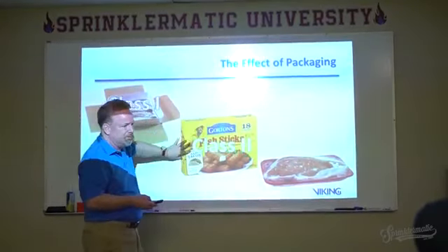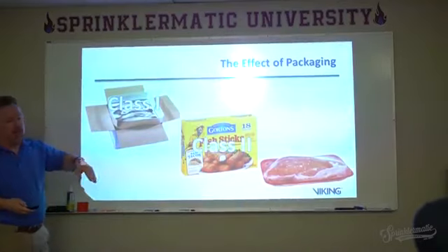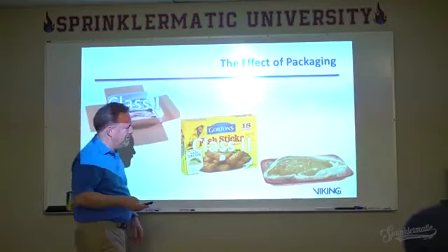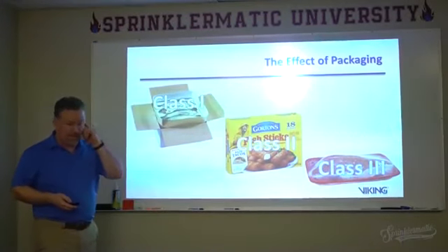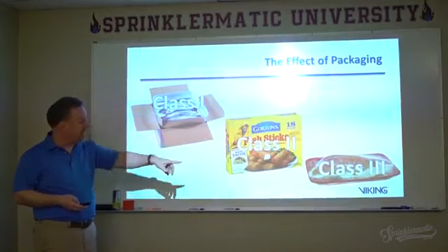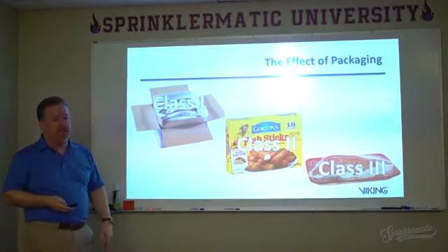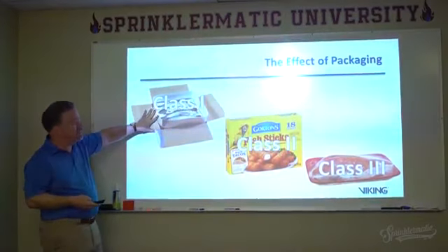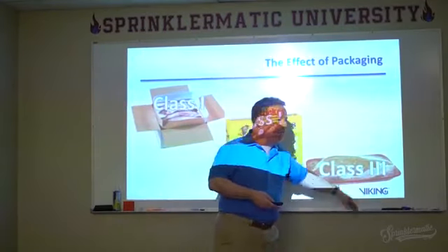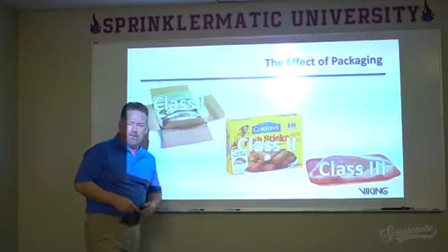It's kind of a wax coated box. That's a class 2. And you take frozen food, you put it on a polystyrene tray. It's class 3. All right, put it on a plastic, not a polystyrene, on a plastic tray. You put it on a regular straight plastic tray, that's class 3. So same stuff, same basic material. We haven't even talked about the pallet or anything else that it's put on. It's going to have a difference depending on how it's packaged.